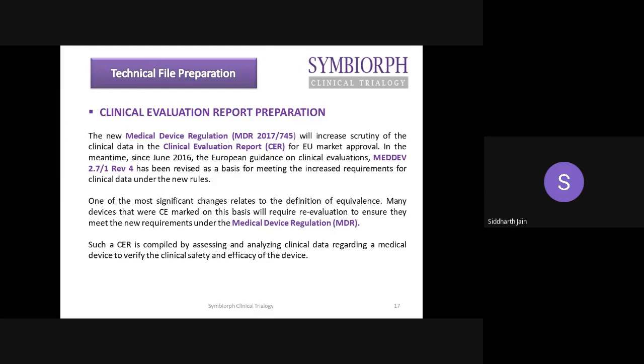One is the MEDDEV 2.7.1 Revision 4, which talks about how to perform the clinical evaluations with the help of the clinical literature, and also how to go for the clinical investigation route. The next important requirement is ISO 14155. You have to prepare the entire clinical protocol, case record form, information brochures, and all these documents you have to submit to the CDSCO for approval, for the no objection certificates, and then only are you eligible to go for the clinical validations.